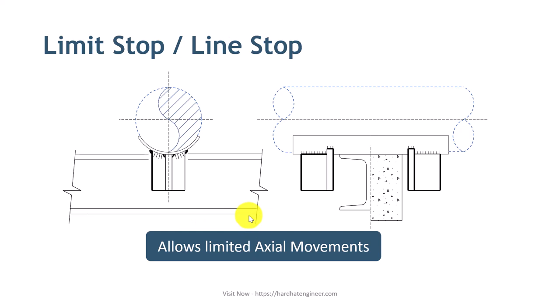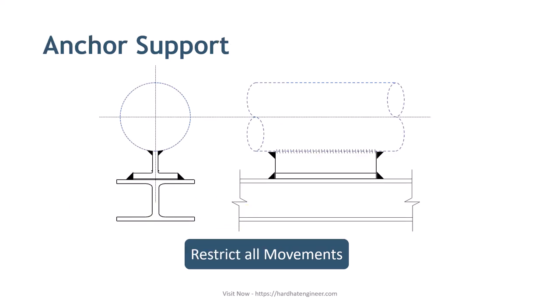Now let's see the function of an anchor in the pipeline. As the name suggests, an anchor restricts all three types of movement in the pipeline at a given point. An anchor aims to divide a pipeline into individual expanding sections. Anchor design should consider all kinds of loads that may occur in the pipeline to withstand any condition that arises during operation. Here in the image you can see that both primary and secondary supports are welded so that the pipe will not move. The primary support is directly connected to the pipeline, and the secondary support is what the primary support rests on. Together they completely stop the movement of the pipe in any direction.